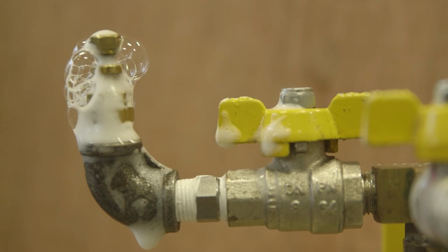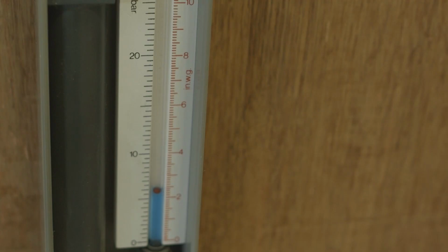The rate of leakage on the installation in this demonstration would result in a complete drop in pressure in less than 2 minutes. The key learning point of this demonstration is that the leak will not become evident until the pressure in the reservoir has dropped below the set point of the regulator. It is very important that the reservoir effect is understood and dealt with appropriately.